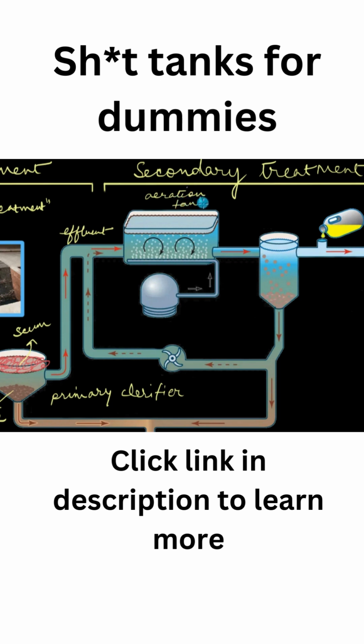So the purpose of this aeration tank is to blow air bubbles into the water, which is done with the help of this air compressor over here. It's an air compressor which is constantly blowing air bubbles into the water, and that increases the levels of oxygen. So the main thing is to increase the level of oxygen in the water. The already present aerobic bacteria and fungi in the water thrive in all of this oxygen and digest the organic matter present. It's like an all-you-can-eat buffet for them.